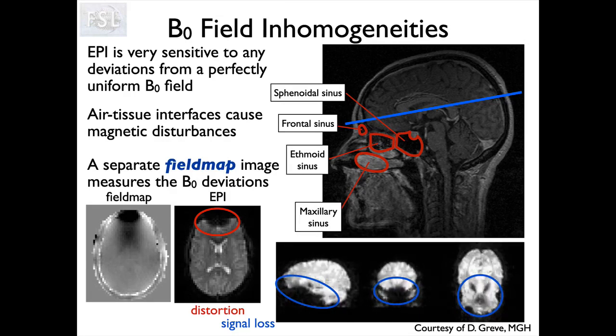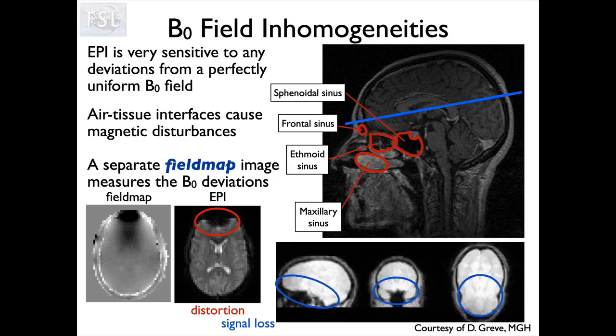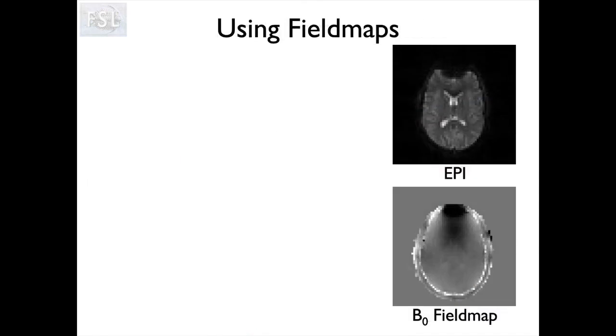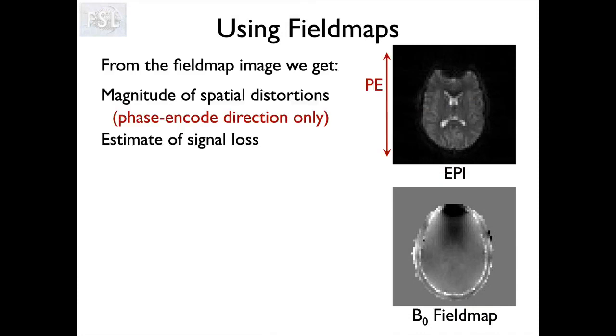We use the field maps to predict how much distortion we're going to get. We already know the direction that distortion will happen — along the phase encode direction, which the operator sets when planning the scan. Typically it's anterior-posterior, but not always. So we can use a field map to estimate the magnitude of the spatial distortion at each location and along which direction, and we can also use it to estimate the amount of signal loss.